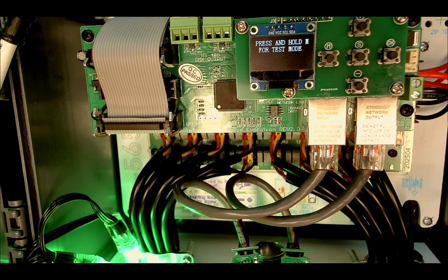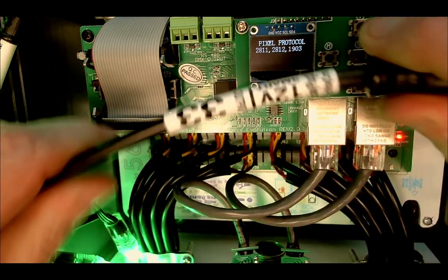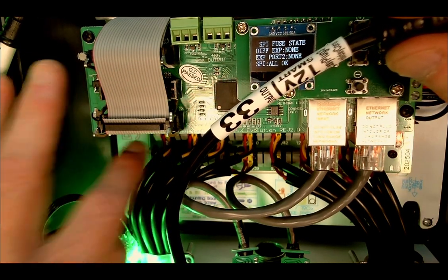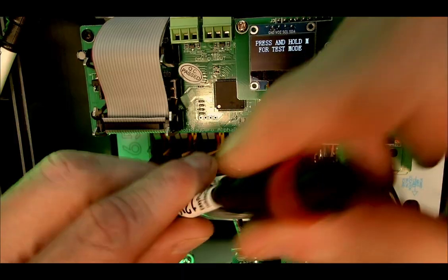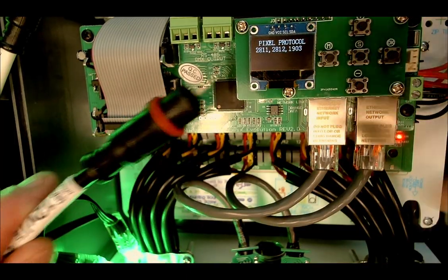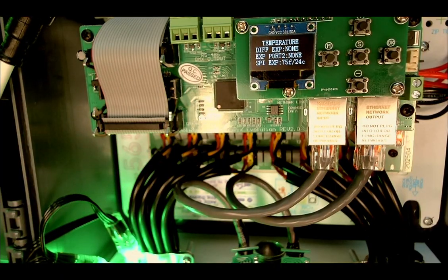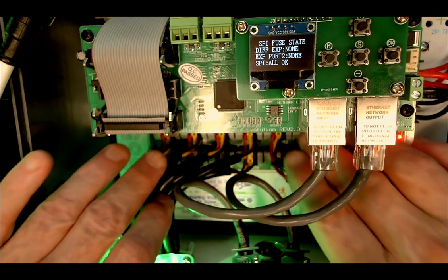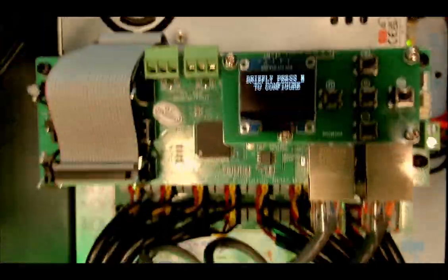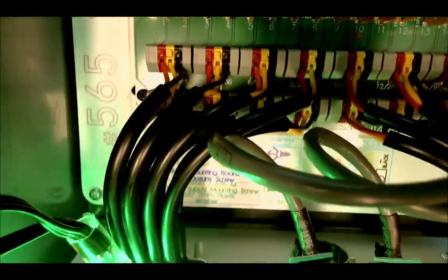All right, so what did we find when we tested that? Let's say that we determined, hey, output 33 doesn't have a blown fuse. It's okay, right? Now, what do we do next? Well, could it be something else? Could it be the cable? Now, rarely do we have problems with the actual cables, so it could be a problem with the connections in the cable.